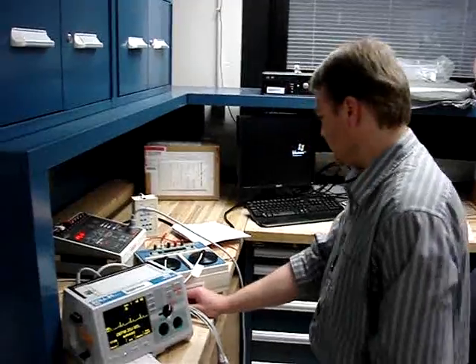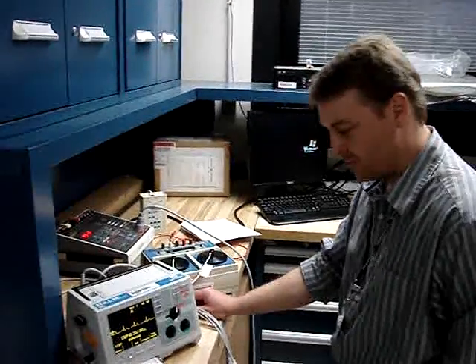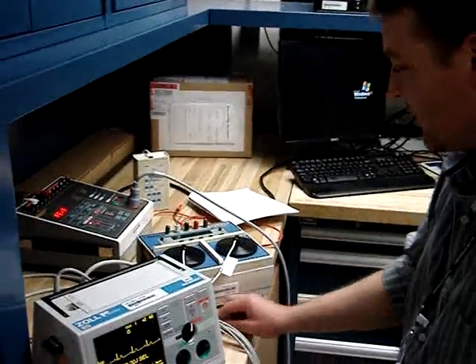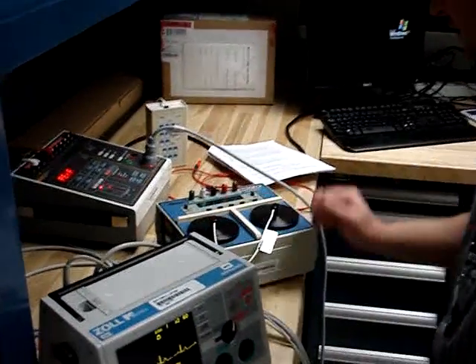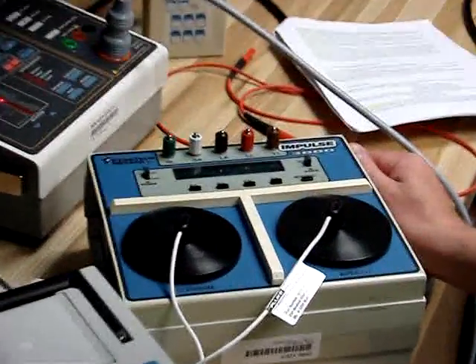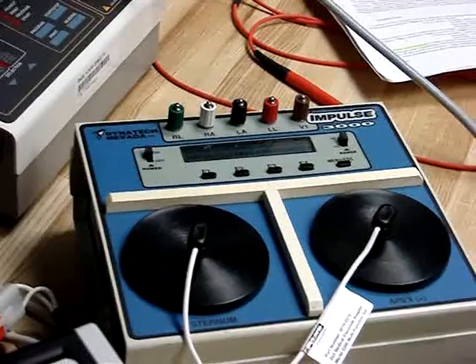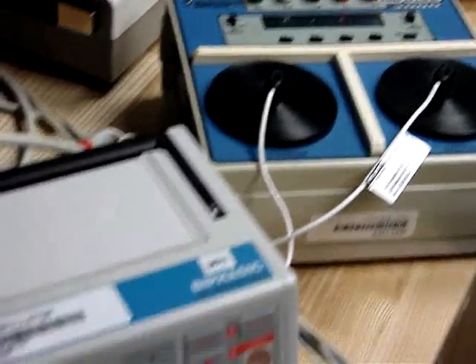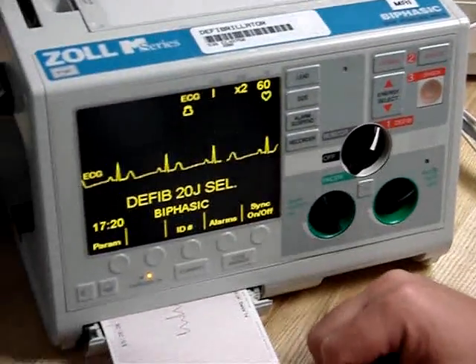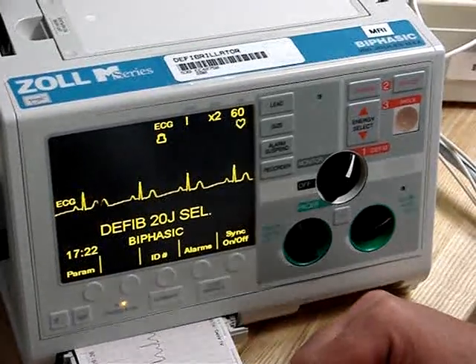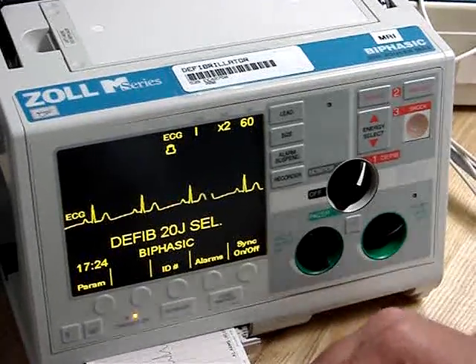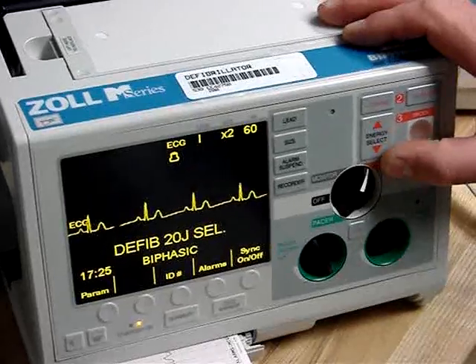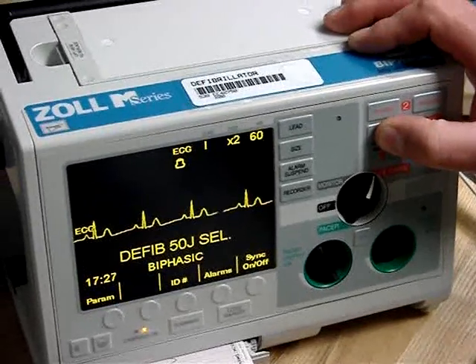Now we'll be checking the energy output levels of the defibrillator. We'll be doing that by first of all having our pads hooked up to the defibrillator analyzer. We're going to have our select switch in defib, and we're going to check the energy levels at 50, 150, and 200. So first we adjust our energy select switch to 50.